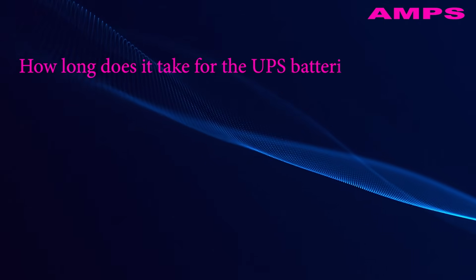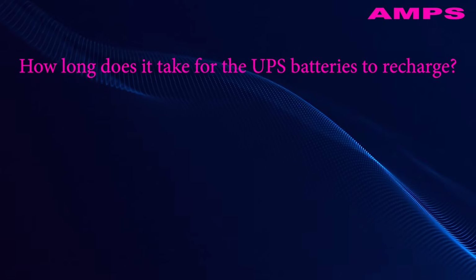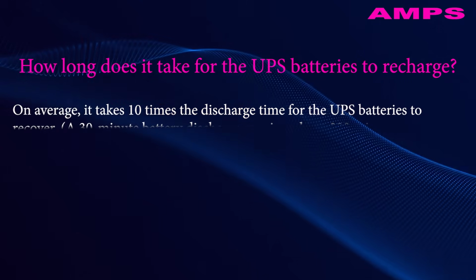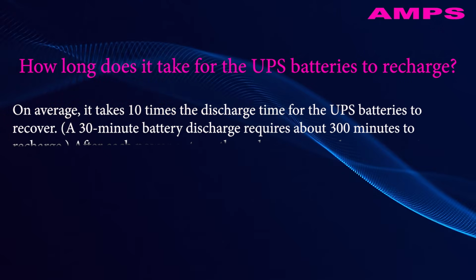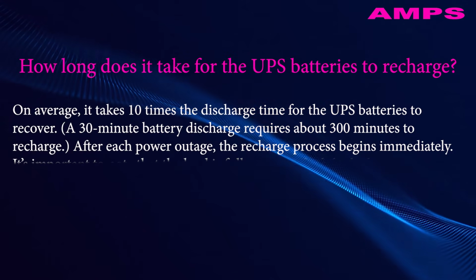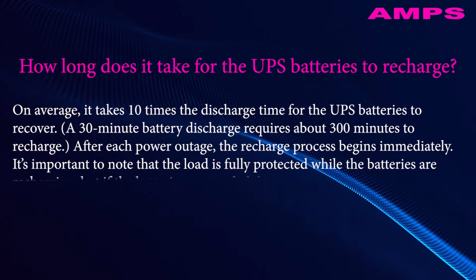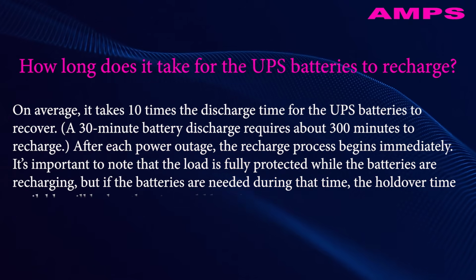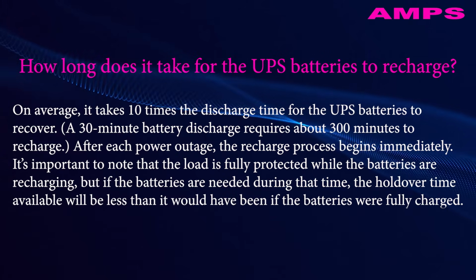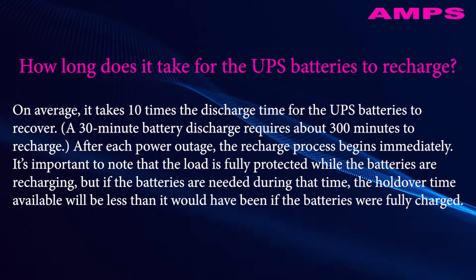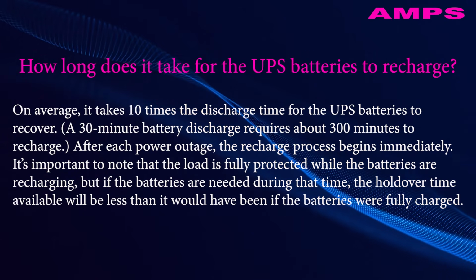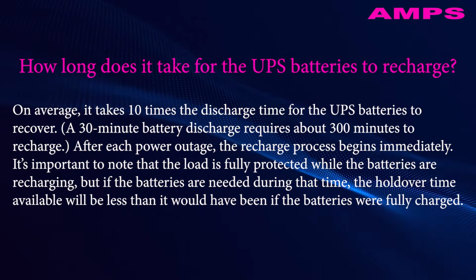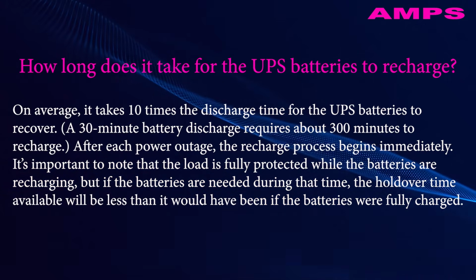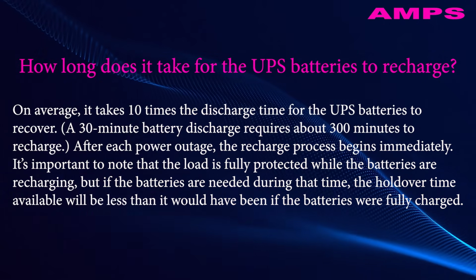How long does it take for the UPS batteries to recharge? On average, it takes 10 times the discharge time for the UPS batteries to recover. A 30-minute battery discharge requires about 300 minutes to recharge. After each power outage, the recharge process begins immediately. It's important to note that the load is fully protected while the batteries are recharging, but if the batteries are needed during that time, the holdover time available will be less than it would have been if the batteries were fully charged.